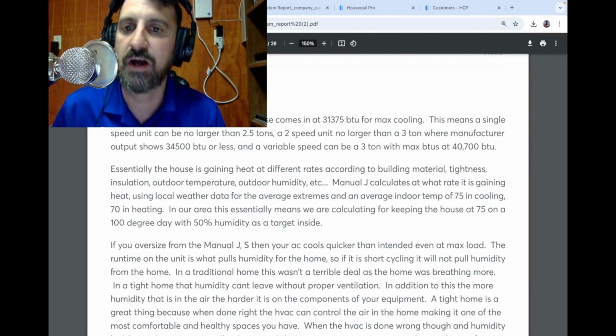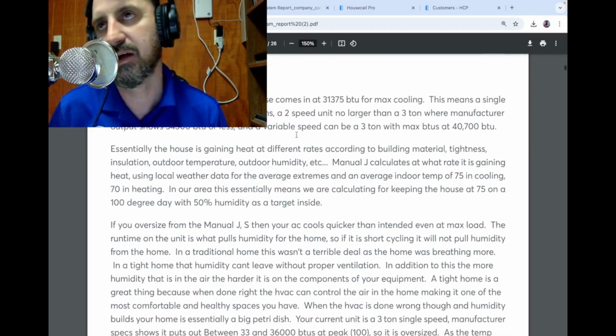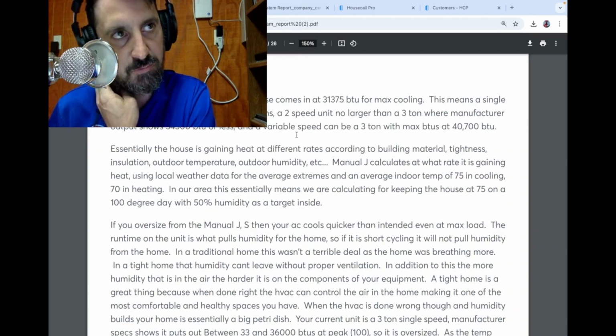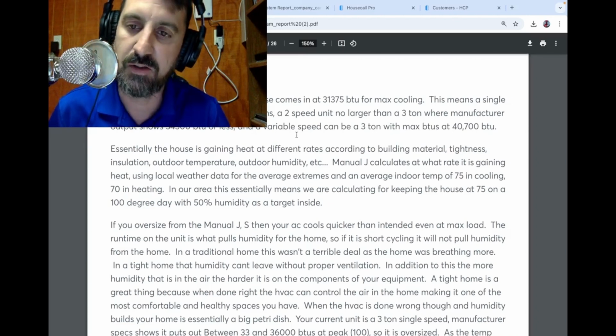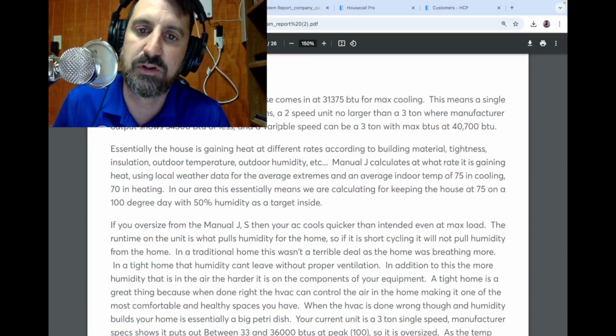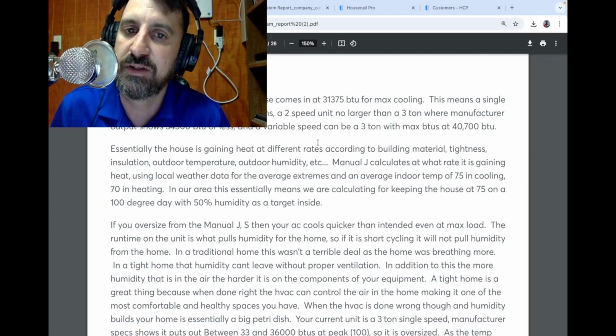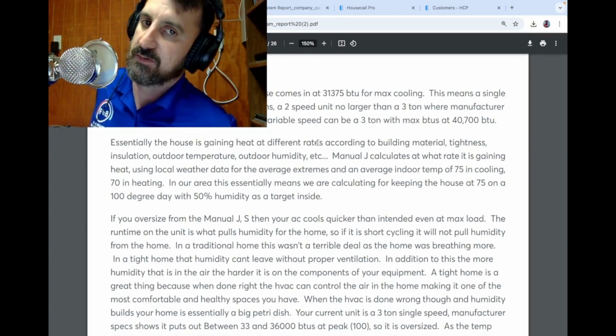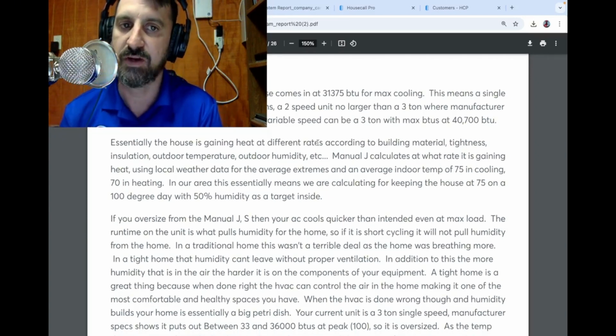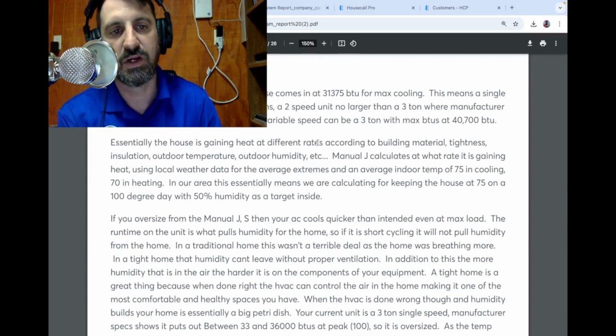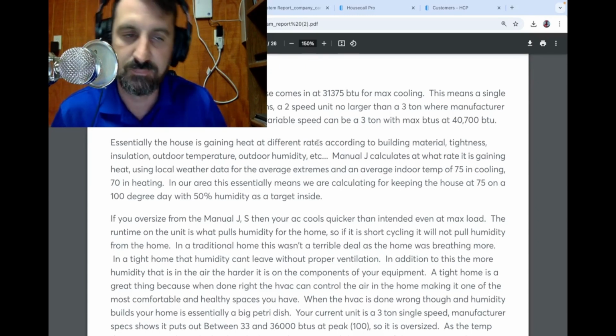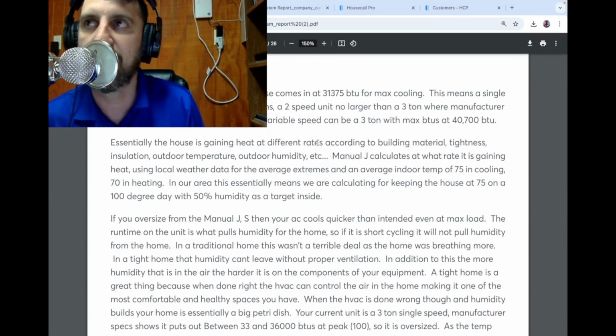So to start off with, I did a manual J on the exterior of the house, more of a block load, so I didn't get a good duct report. But essentially, the house comes in at 31,375 BTU for max cooling. That's the max load on the house.